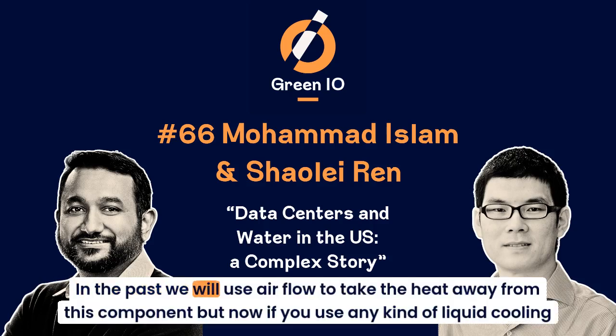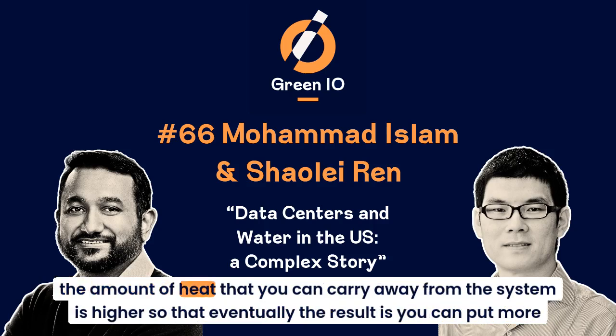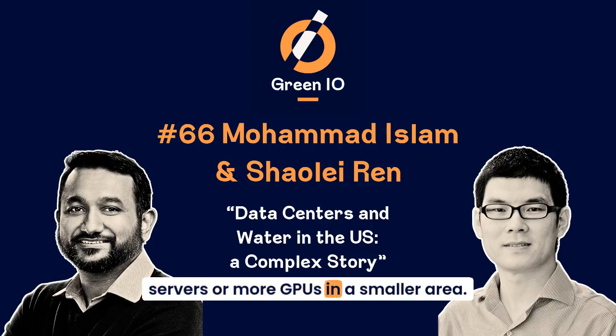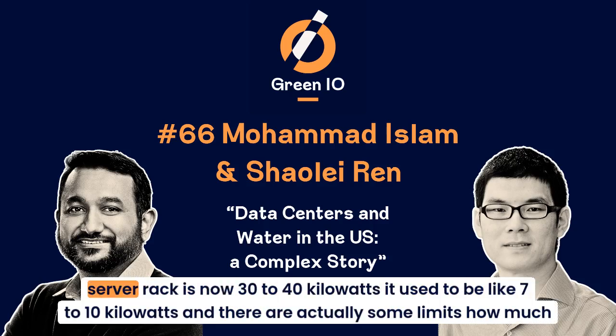In the past, we would use airflow to take heat away from those components. But now with liquid cooling, the amount of heat you can carry away is higher, so you can put more servers or GPUs in a smaller area. These days, the power footprint of a server rack is 30 to 40 kilowatts; it used to be 7 to 10 kilowatts.